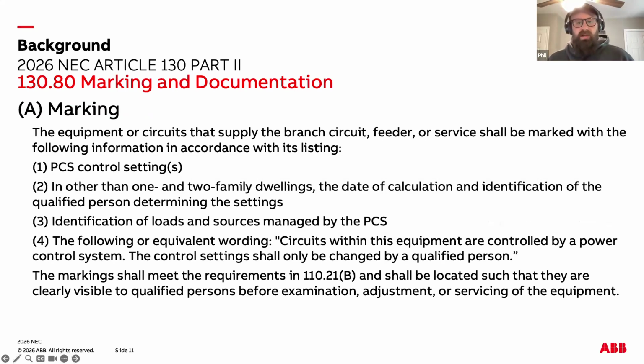130.80 deals with marking and documentation. Just like you have to label a panel anytime you install a circuit or put up your PV disconnect label, there are specific requirements for labeling a PCS installation. 130.80 can be summarized as a labeling and documentation rule for any equipment or circuit supplied by a PCS. It ensures that anyone servicing the system understands the PCS limits, who set them, and which circuits are affected.